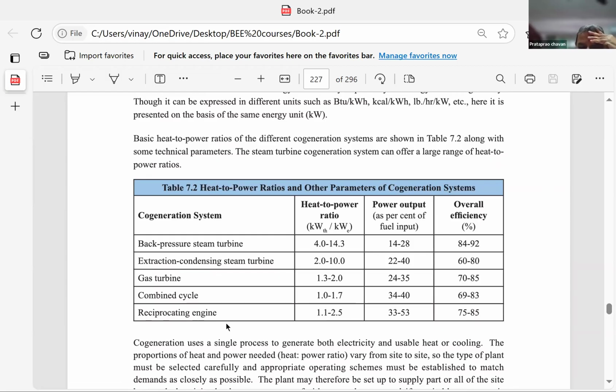For reciprocating engines, the process steam is secondary; main production is electricity. So power output as percent of fuel input is minimum in back pressure, maximum in combined cycle and reciprocating engines. In MCQs, you may be asked the heat to power ratio or the power output percentage for a particular case, and you have to correctly choose it.